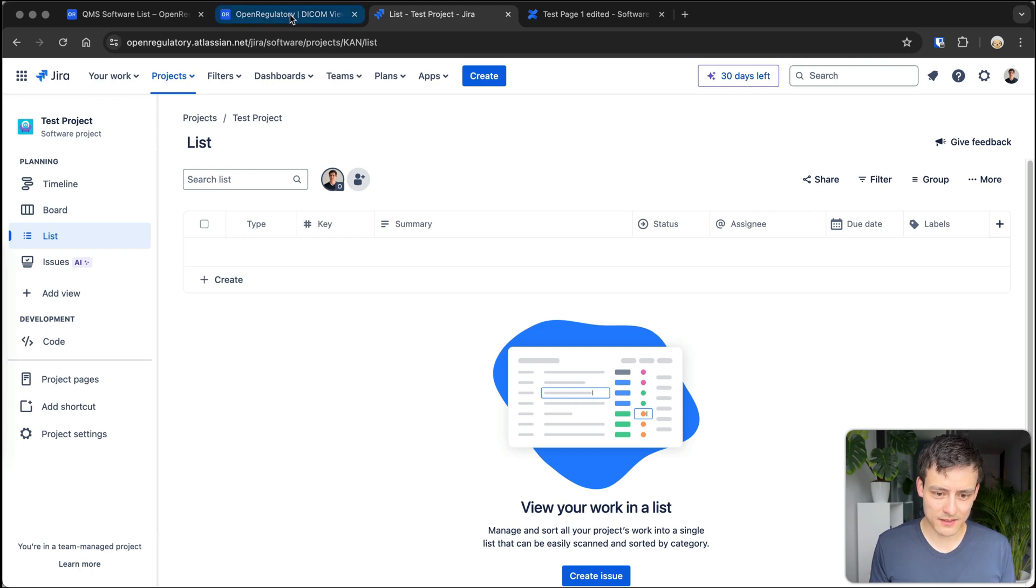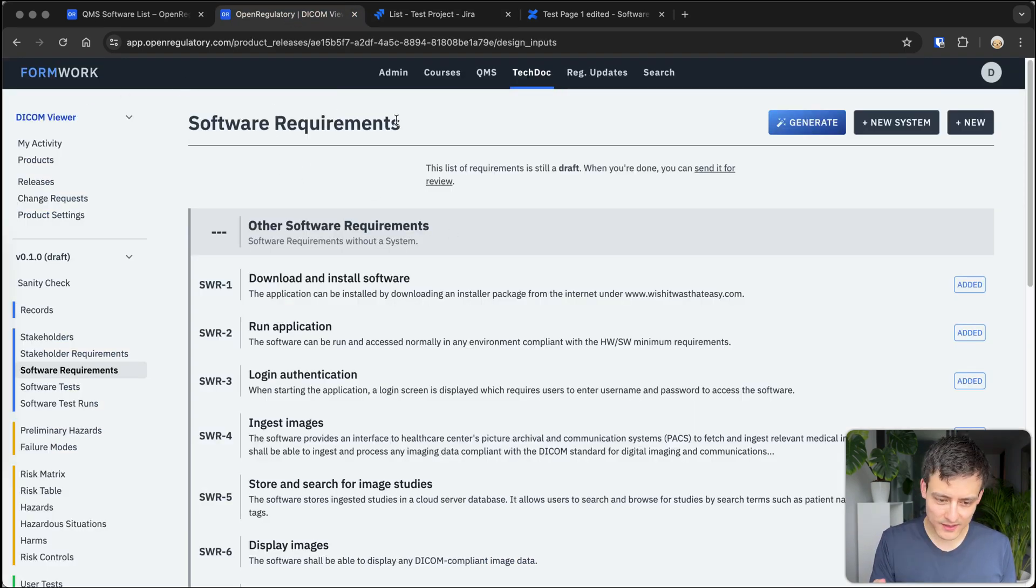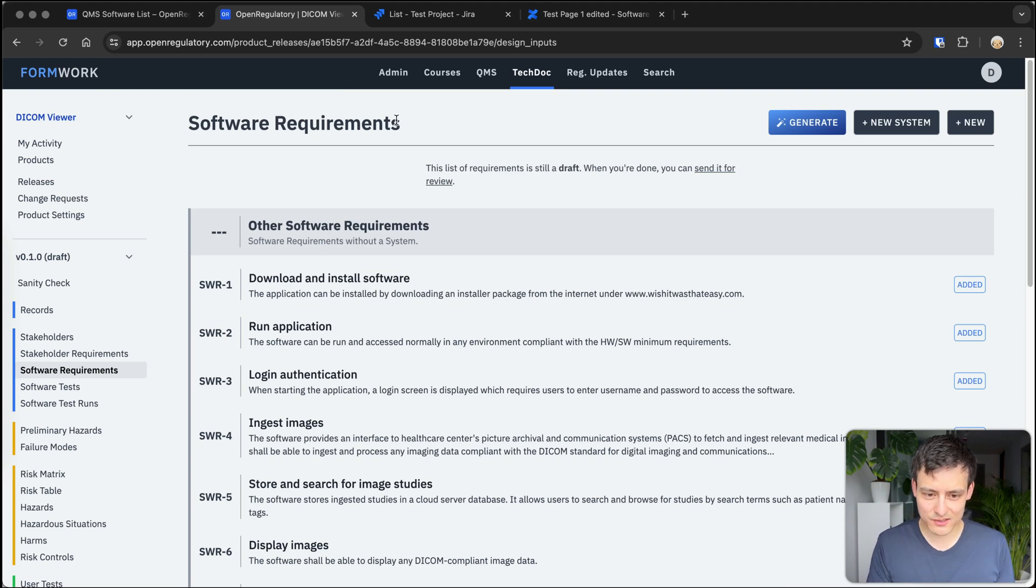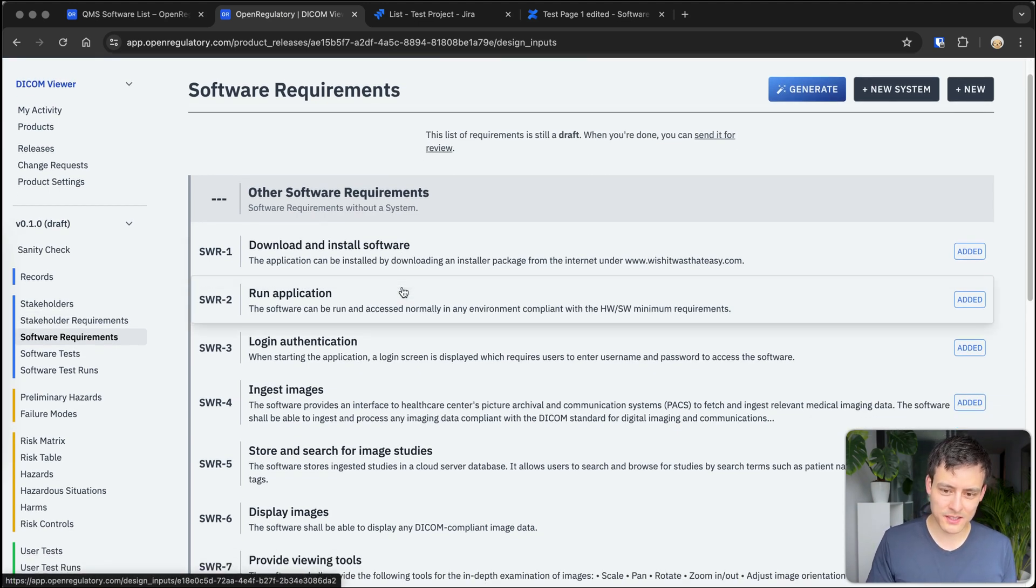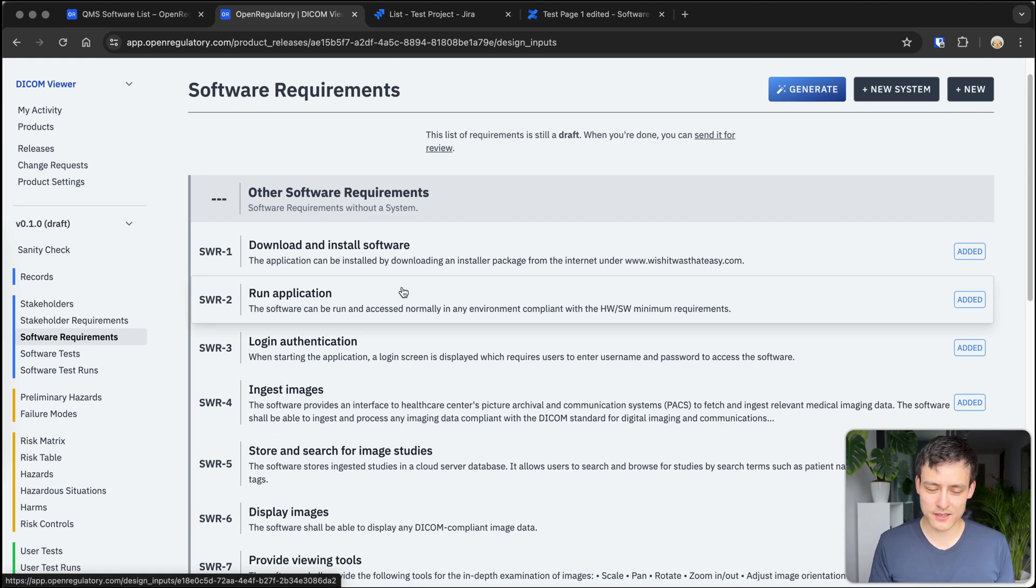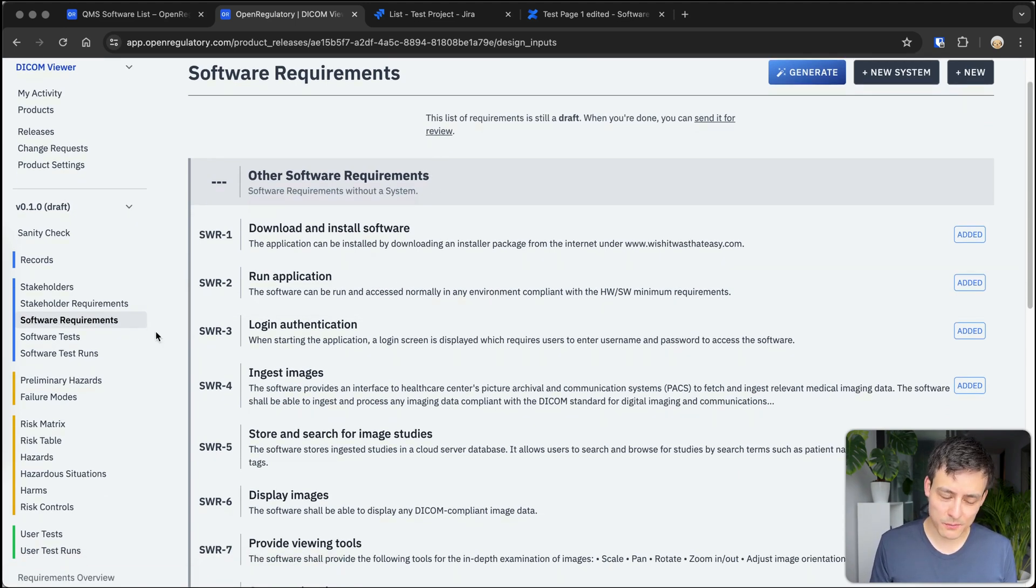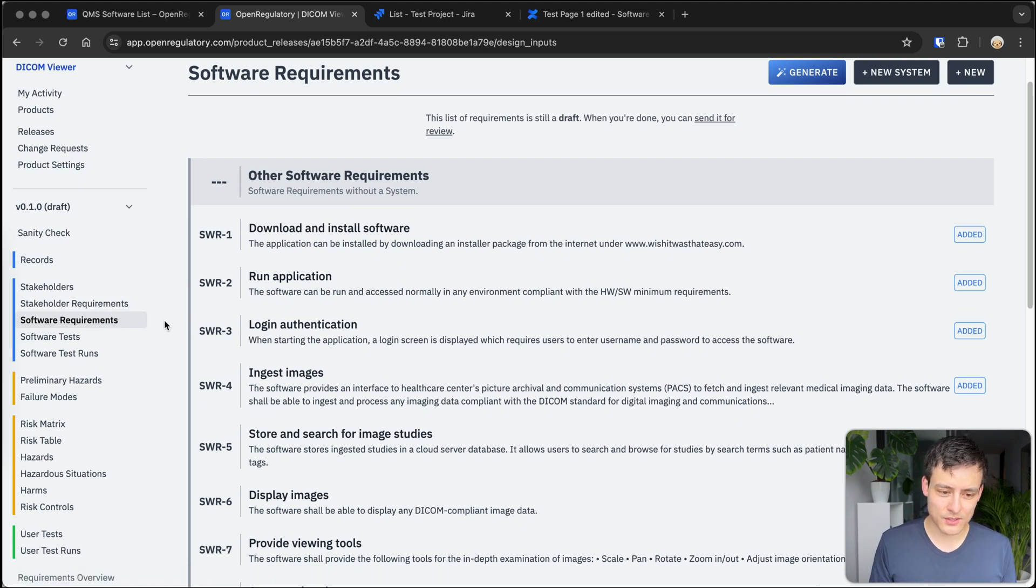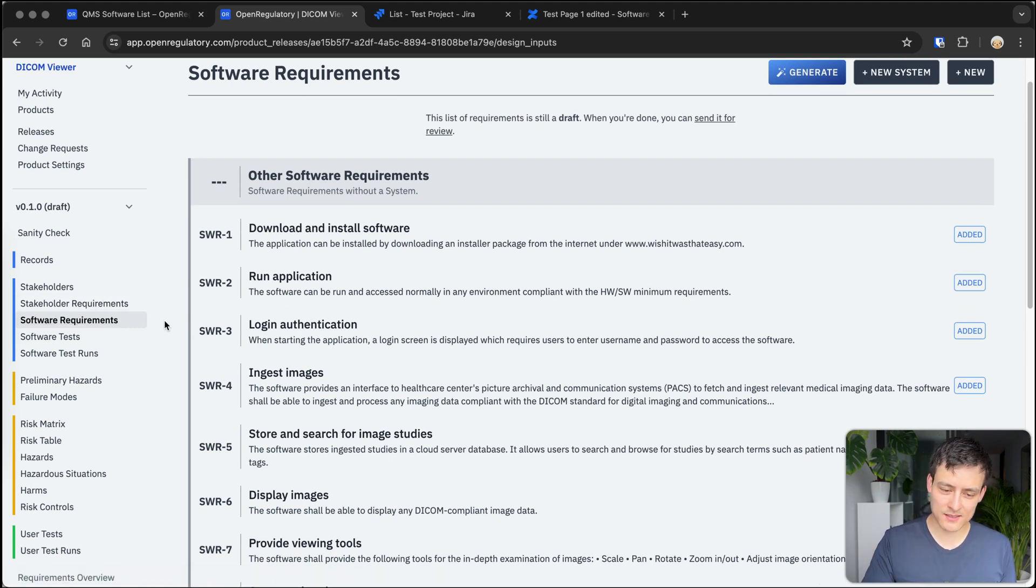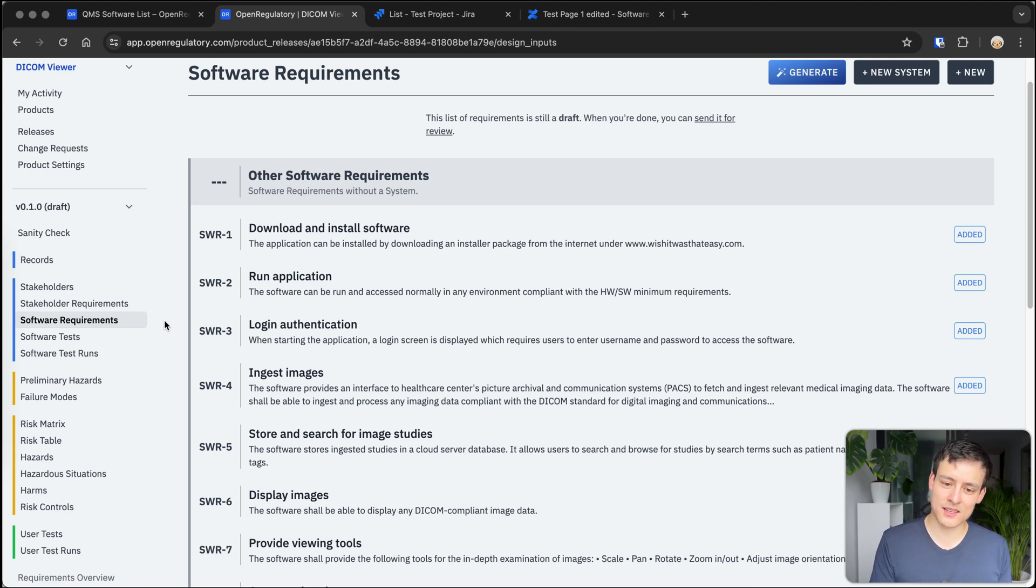So in our compliance documentation software Formwork, I'm actually not necessarily trying to promote it here, I'm just trying to show you how content-wise a regulatory submission would look like for medical device software. So you have something called software requirements or design inputs, and those are essentially a specification of your software. So it's a list of, in simplified terms, a list of features which you can then send to your auditors.